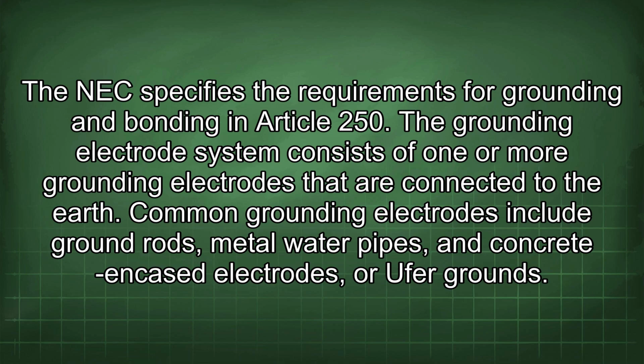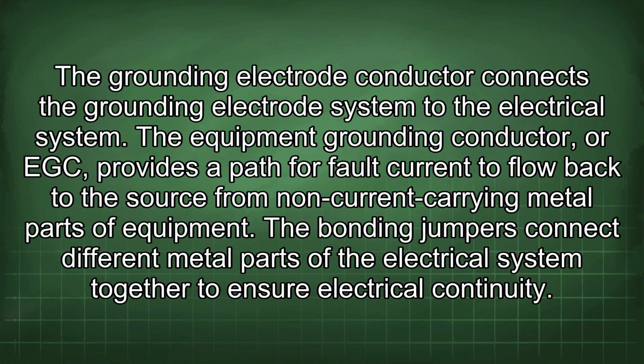The grounding electrode system consists of one or more grounding electrodes that are connected to the earth. Common grounding electrodes include ground rods, metal water pipes, and concrete encased electrodes, or Ufer grounds. The grounding electrode conductor connects the grounding electrode system to the electrical system. The equipment grounding conductor, or EGC, provides a path for fault current to flow back to the source from non-current-carrying metal parts of equipment. The bonding jumpers connect different metal parts of the electrical system together to ensure electrical continuity.